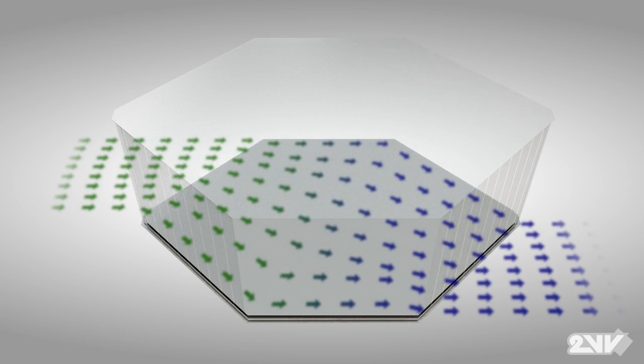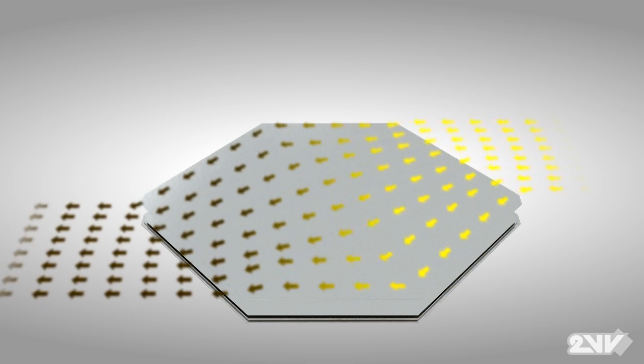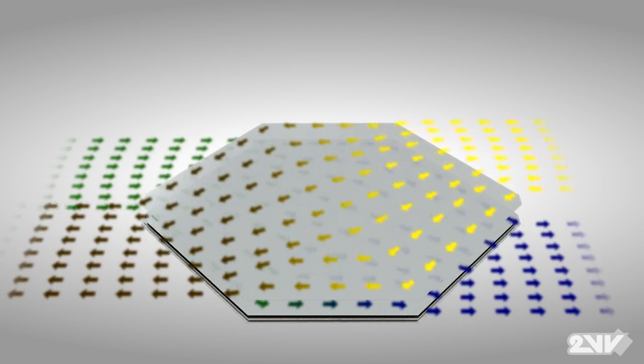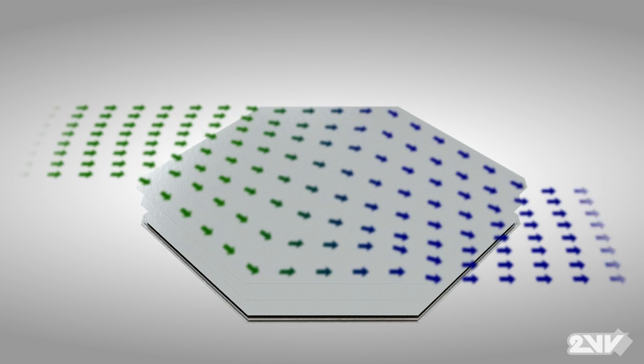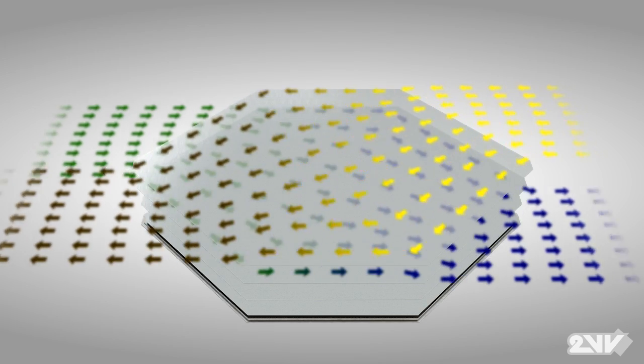As fresh outside air passes through channels by way of stacked aluminium plates, warmer interior and exhaust air passes through separate channels in the opposite direction. The subsequent effect is a transfer through conduction of heat from the interior air to the outside air. Layers upon layers of aluminium plates creating multiple channels results in a recovery of heat, which normally would be lost in a typical non-heat recovery system.